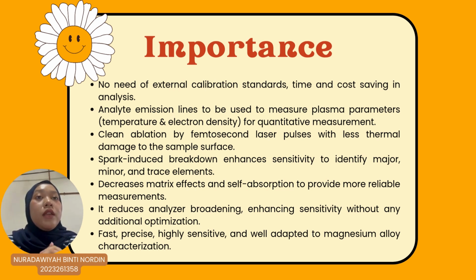Calibration-free femtosecond laser ablation spark-induced breakdown spectroscopy is highly valuable for the elemental analysis of magnesium alloys due to its ability to deliver accurate results without the need for external calibration standards. This technique relies on the analyte emission lines to determine key plasma parameters such as temperature and electron density, which are then used to calculate elemental concentration.